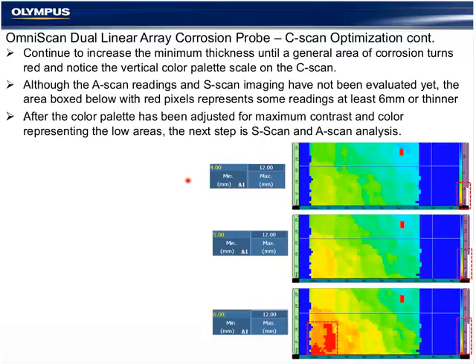I'm going to continue doing that until we see areas of severe corrosion, either a single area or several areas. As I'm increasing or reducing the color palette range, I'm scaling the color over my thickness as an indication of where trouble spots are. This might be an isolated pit or something that contaminated the gate. This looks like a more realistic area of corrosion. I'm just doing this on the C-scan first without the benefit of the A and the S scan.